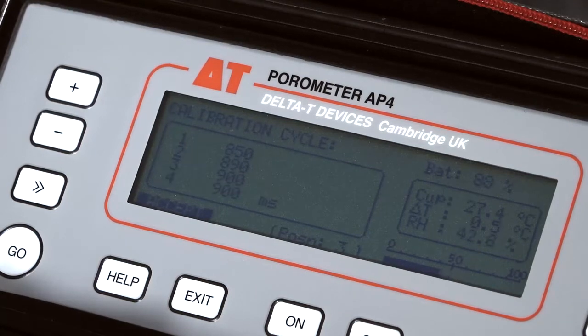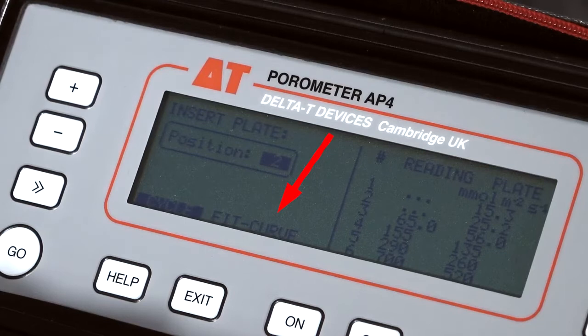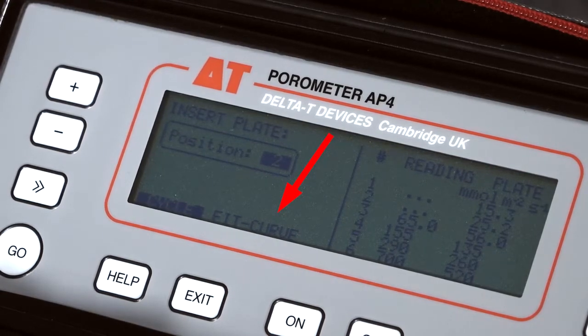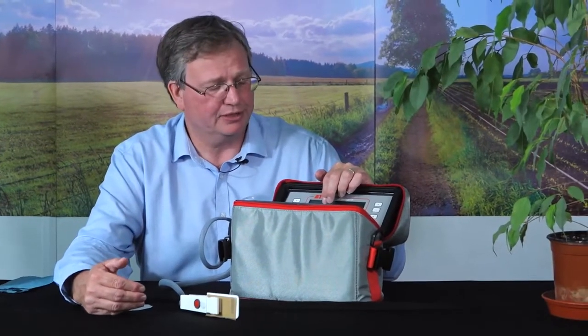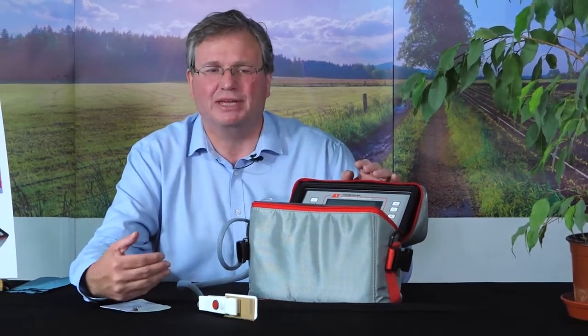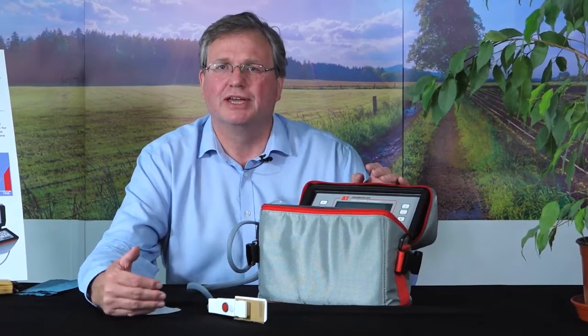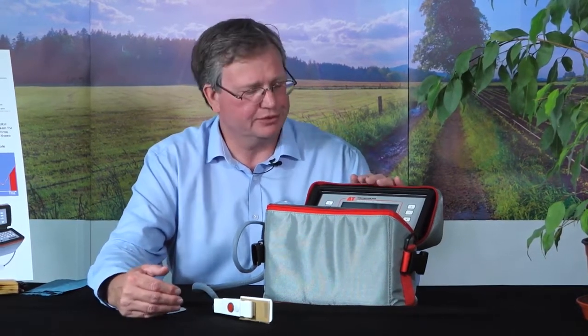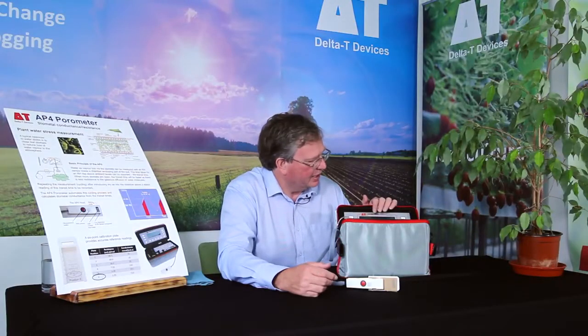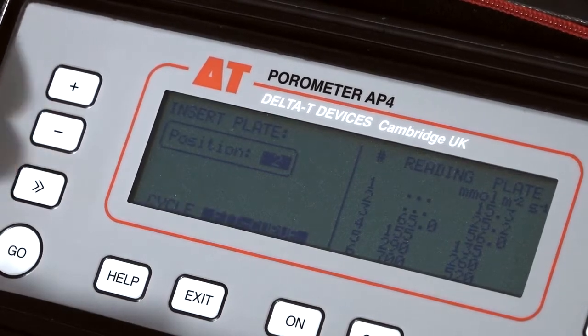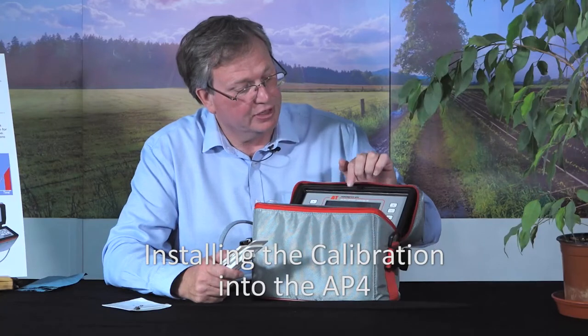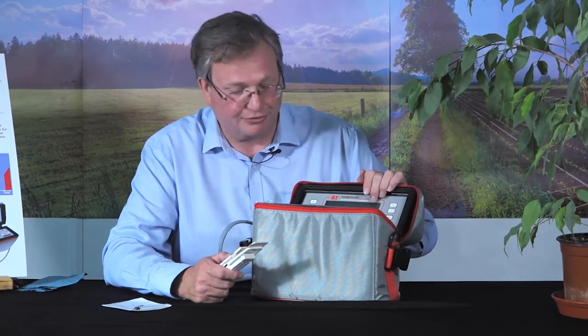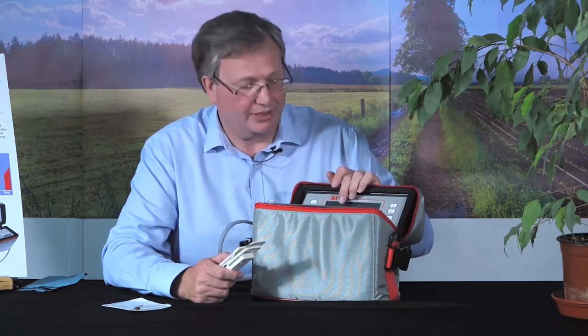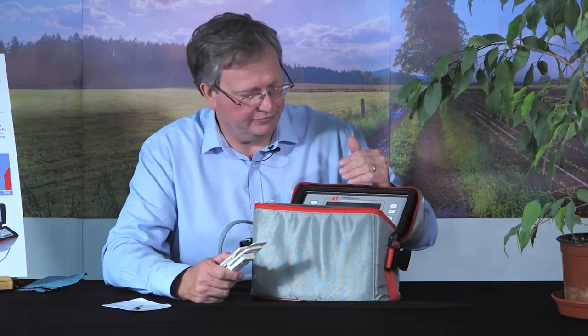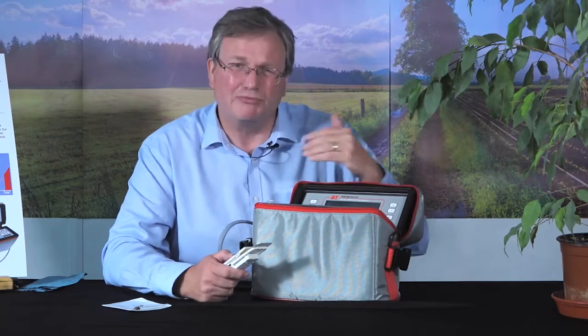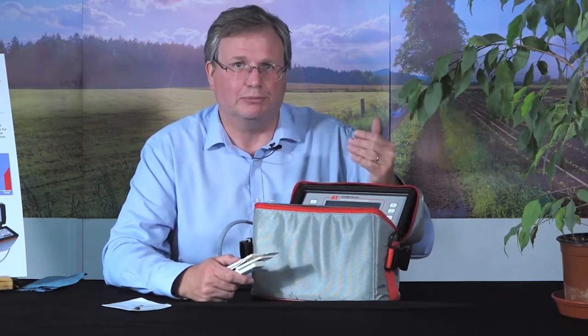And when I accept this reading, the Porometer gives me an option after 4 points to fit a calibration curve. We'd recommend, if you can, carry on for the full 6-point calibration. Sometimes the local conditions make this difficult. Check the manual. There's a chapter on this, explains why you might want to stop at 4 points. A 4-point calibration curve is perfectly valid. To select that, we scroll across to fit the curve. And what this means is that the Porometer will compare the theoretical values against the actual values we just measured. So if I select fit curve now, the Porometer will estimate the error for that curve fit. And that's what I'll do now. We'd recommend you really to carry on with all 6 positions, but a 4-point calibration curve is quite valid.